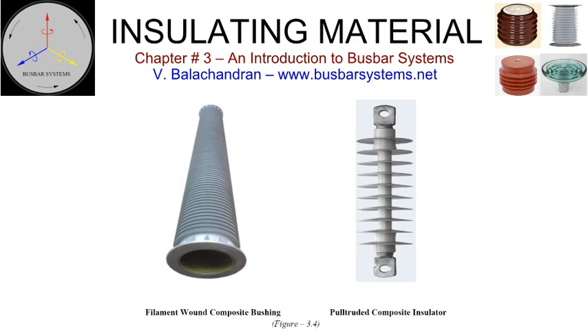Lightning arrestor housings are also made of composites since filament wound tubes can withstand very high pressures and do not shatter when absorbing the energy of an electrical surge. Shattering of lightning arrestor housing can damage expensive switchyard equipment in the vicinity of its installation.